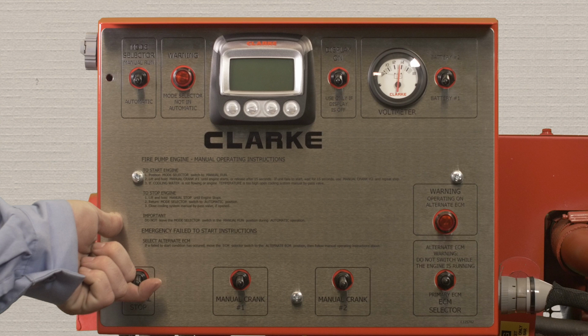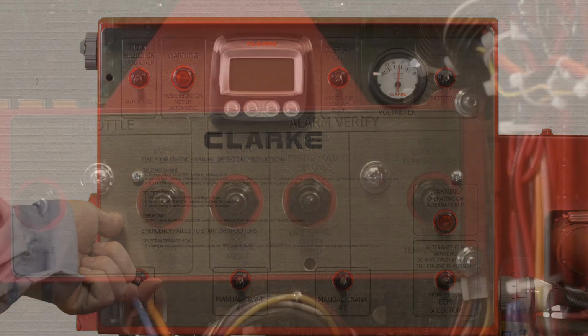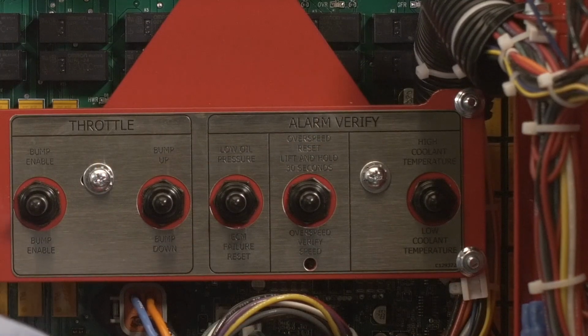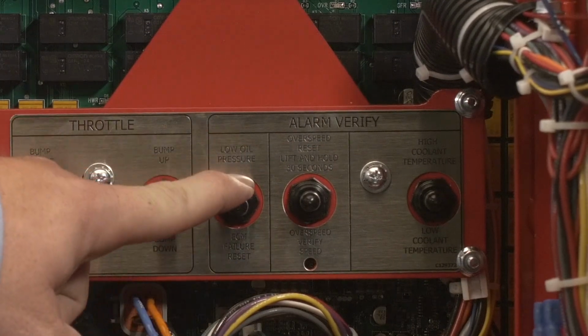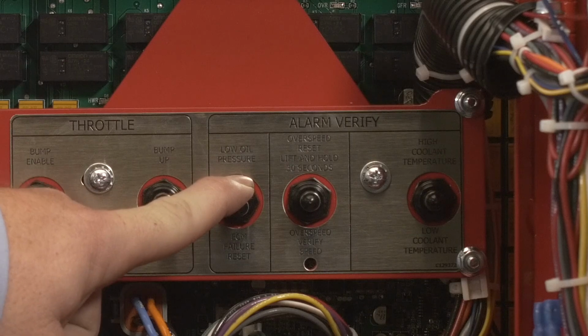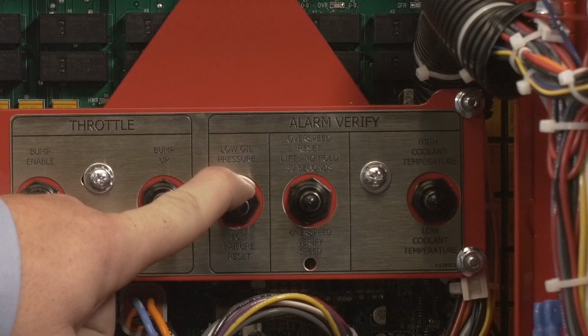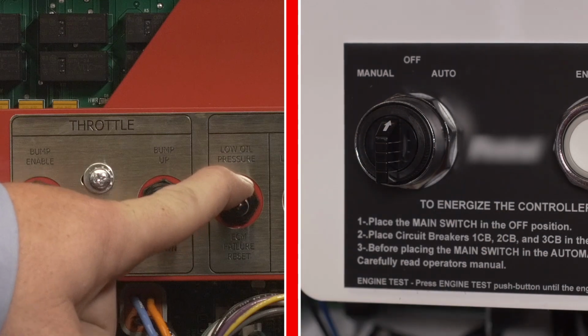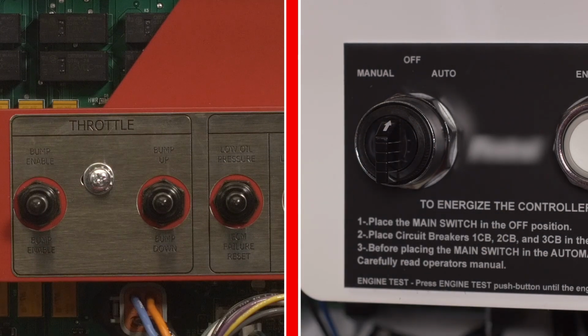Once the ECM failure alarms have been simulated, you must reset the ECM with the ECM failure reset switch. To do this, hold the ECM failure reset switch down for 3 seconds. Reset most pump controllers by turning the selector switch to the off position.